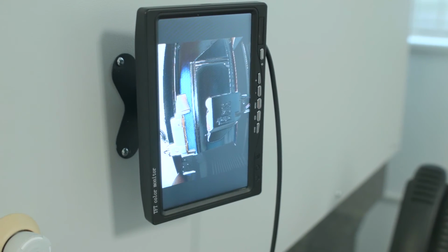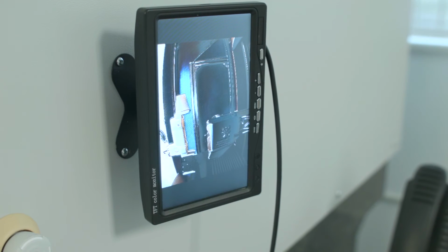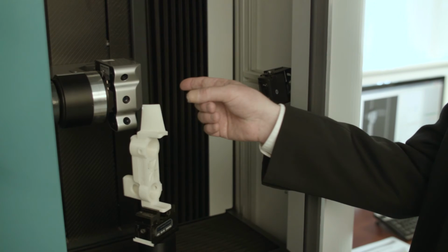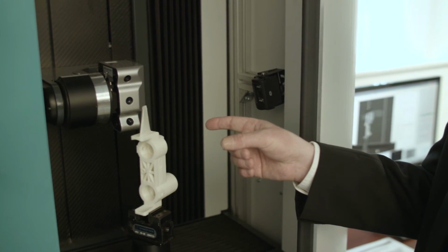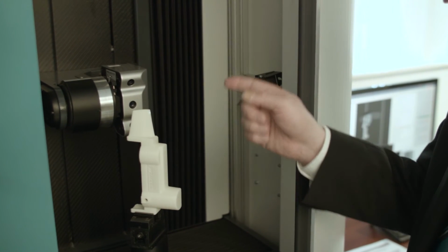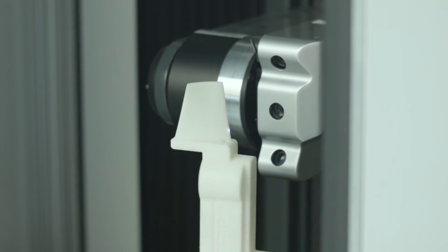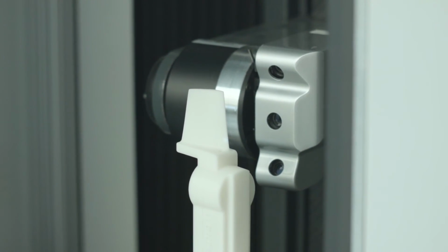So the way the machine works is that it has a spot of light, a beam of light, coming from the center of those three windows. There's a camera in the top and there's a camera in the bottom. So that means that your access with all these rotary movements is extremely good. You can get on all surfaces, though you can't go that deeply down holes. So if there's a lot of holes to be measured, this is not the technology for you.